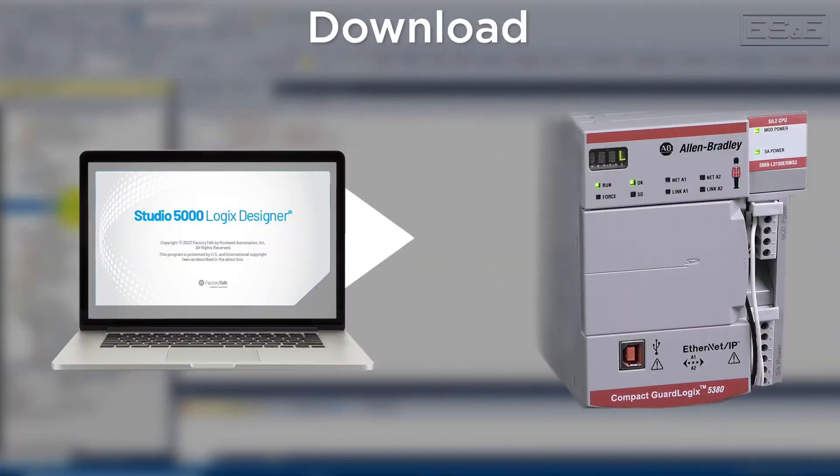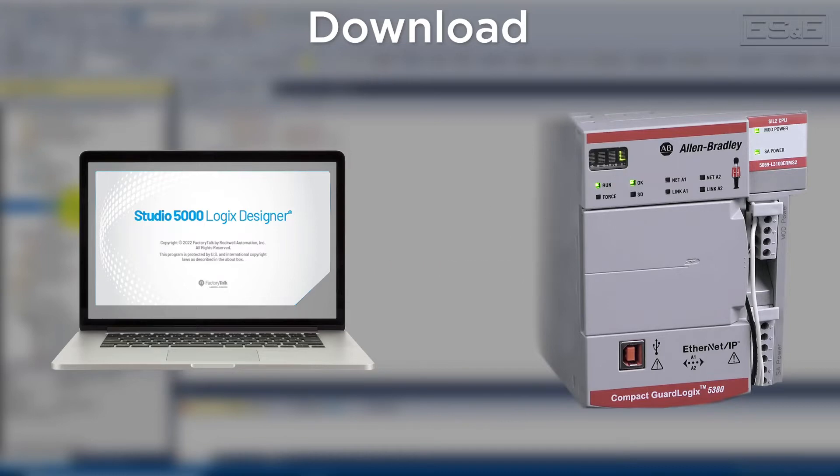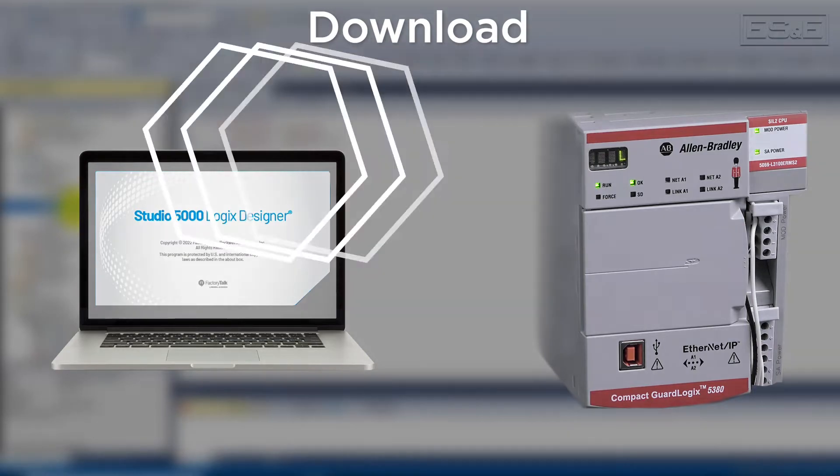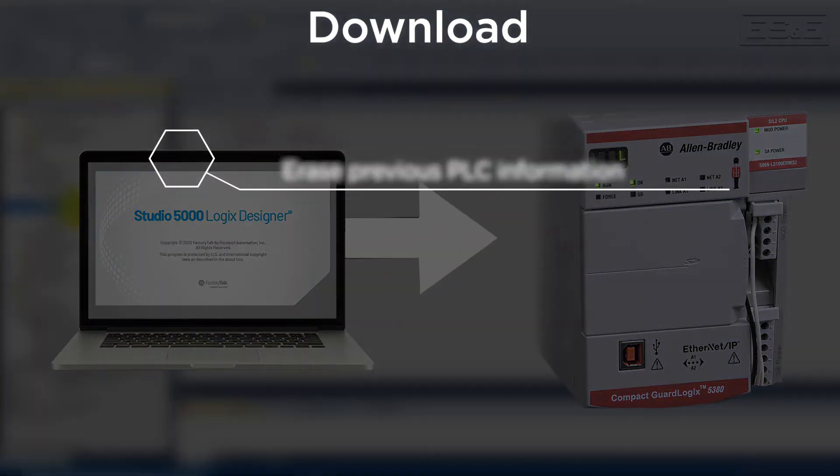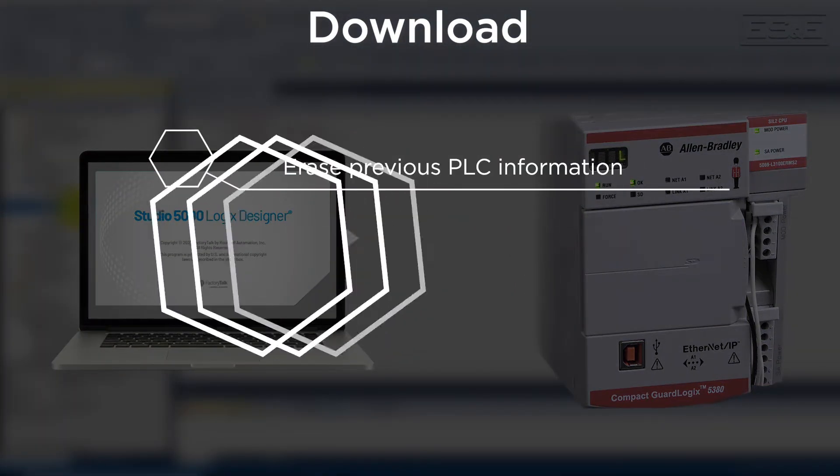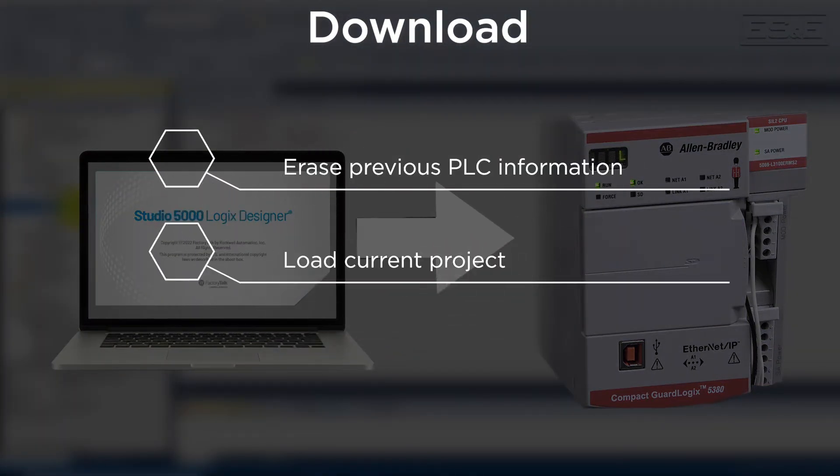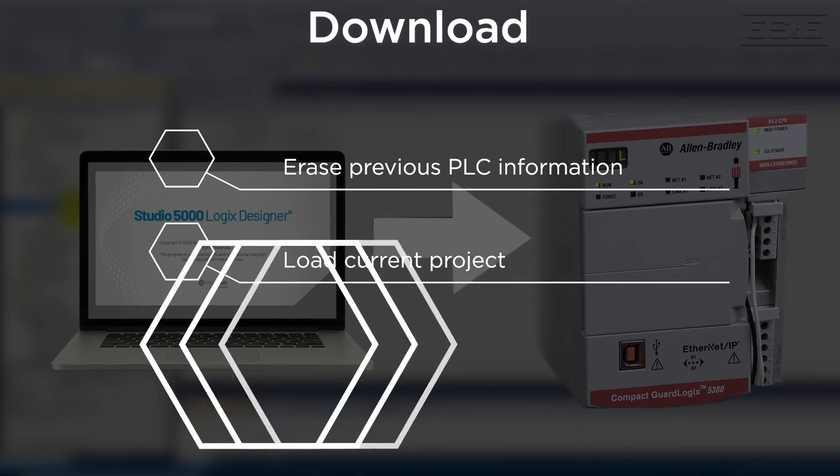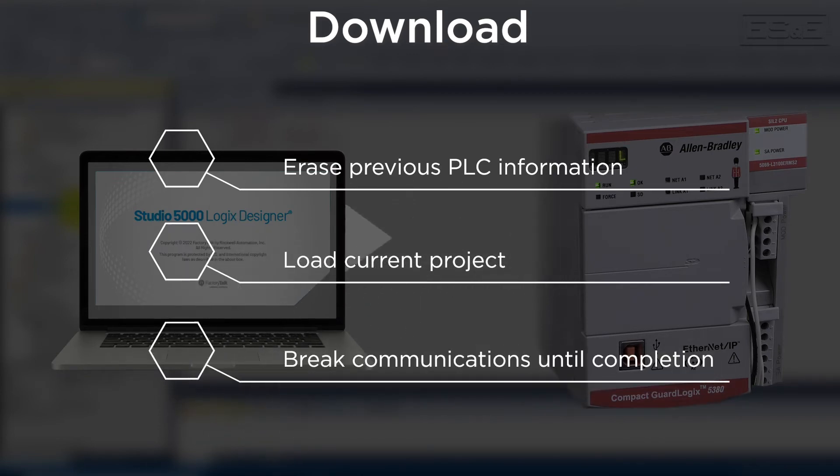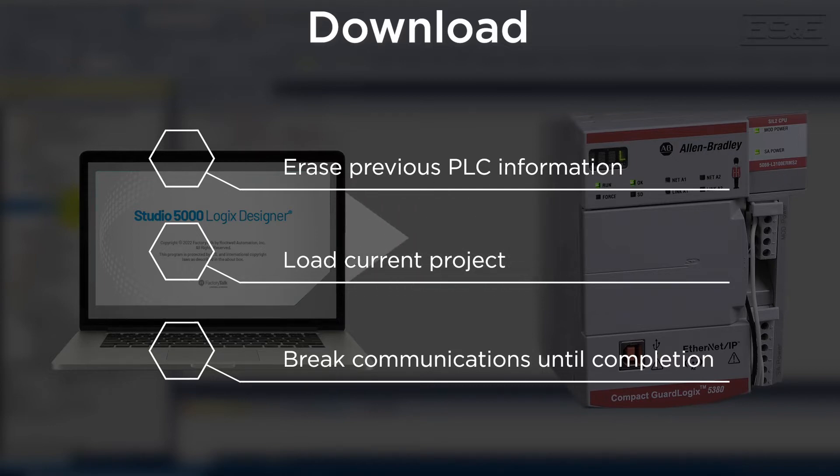Once your project is configured, the next step is to transfer it from your computer to the PLC. For all Rockwell software, downloads will compile the project file or the ACD from the computer and download it into the controller. This action will erase everything that is in the controller and load it with what you have on the PC. It will also break all other forms of communications until the download is complete.